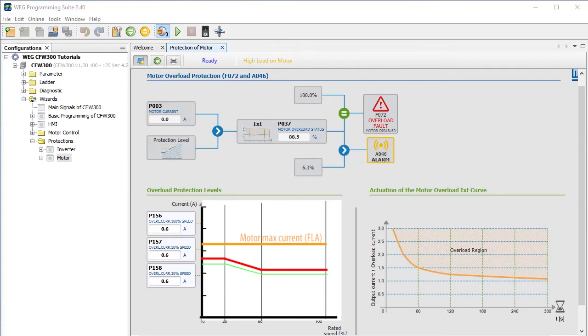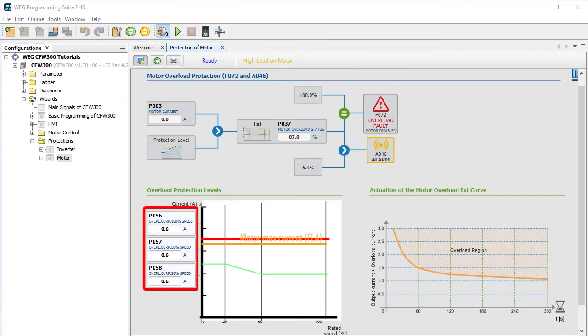If we just wanted to protect the motor, we would simply look at the full load amps on the nameplate, add a little — 10% is usually pretty good — and use that for these overload threshold numbers. Now we would be protecting the motor from burning itself out. Exact same process, just a different point of view.